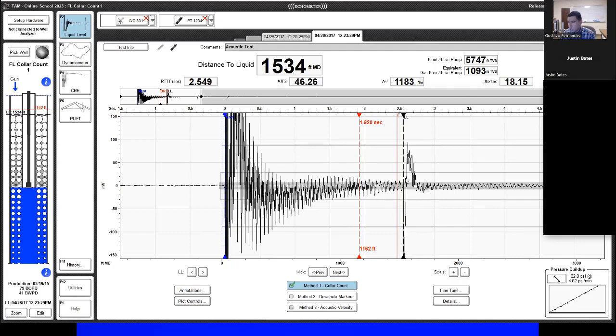To recap and close this topic, selecting liquid level gives you time. We will use one of the methods to calculate acoustic velocity. We're now talking about method 1, using the collar count. The C line will represent the last collar, and the software has done an excellent job counting collars. If you have input the right average joint length, the software will be calculating a good distance and average acoustic velocity. Now with velocity and time, the software will calculate an accurate distance to liquid.